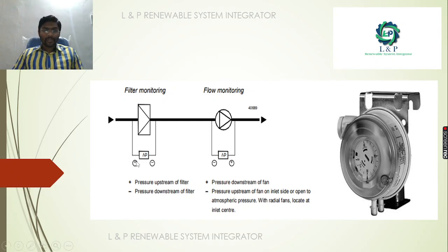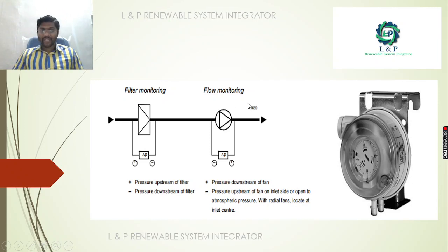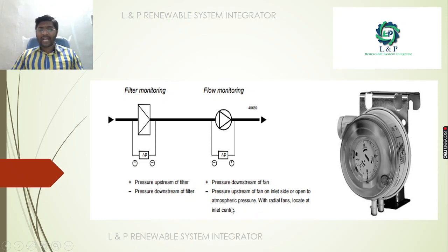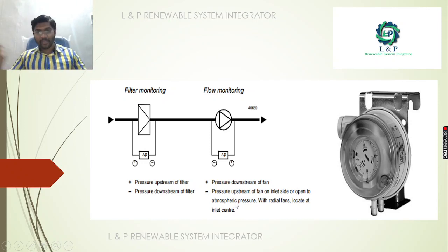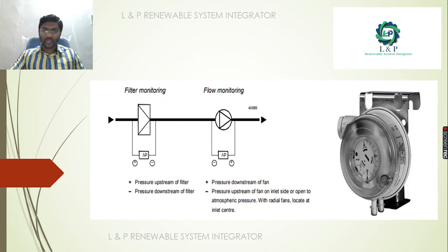When used for filter monitoring, the positive side is used for pressure upstream and the negative side for pressure downstream. For monitoring flow, the positive side is used for pressure downstream of the fan and the negative side for pressure upstream. Sometimes, if there is no provision to connect the upstream, you can connect the negative point open to atmospheric pressure — it will compare with atmospheric pressure against the set point, and if the difference exceeds the set point, it will close the contact from NO to NC.